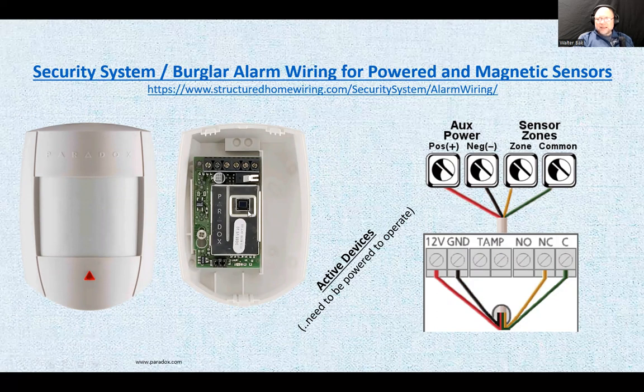Okay. And one of the most common ways of detection is infrared, the infrared field change. For example, we humans transmit certain infrared waves around us, so that thing can see that, and it has to change in order to trigger. So if you're moving from one spot to another, that thing is going to sense it, and it's going to trigger into an alarm condition, which means it is going to open these 2. So at ease, these things are closed. Here's the zone. These are the dry contacts right here, normally closed, which means at ease it's closed.